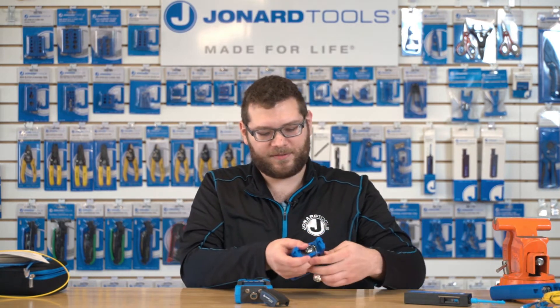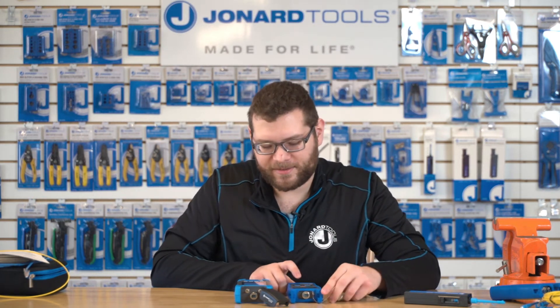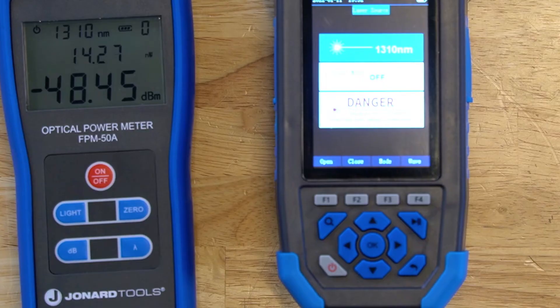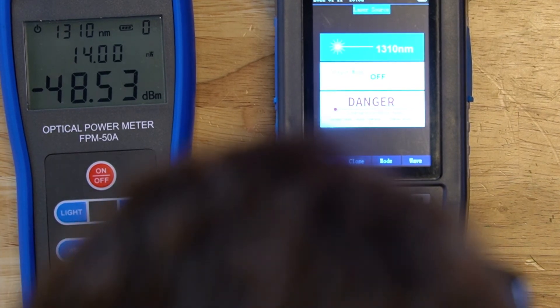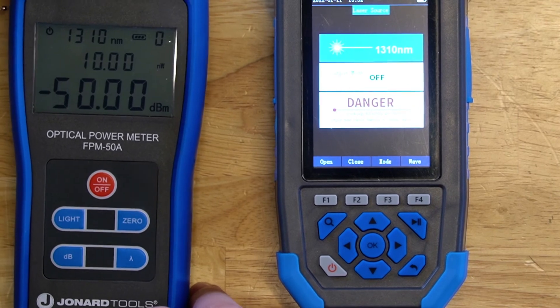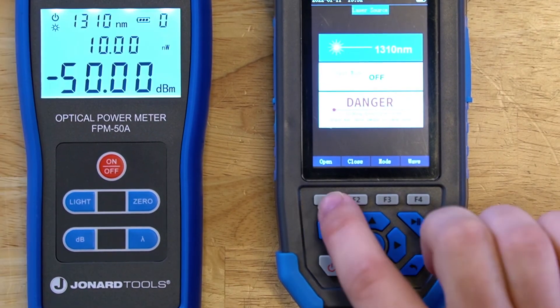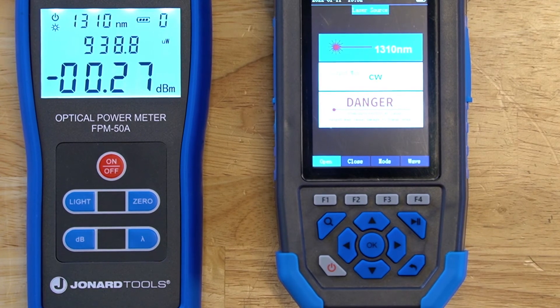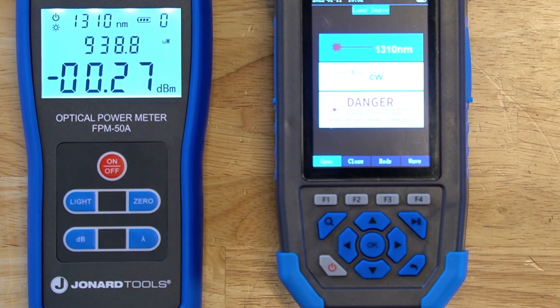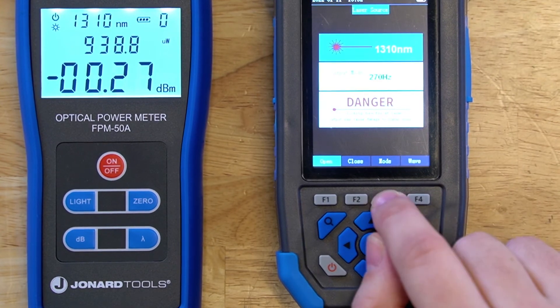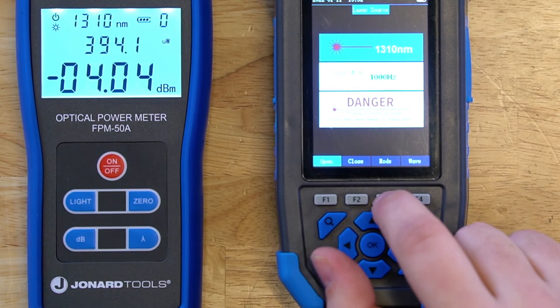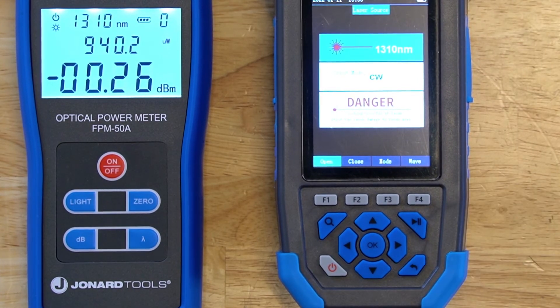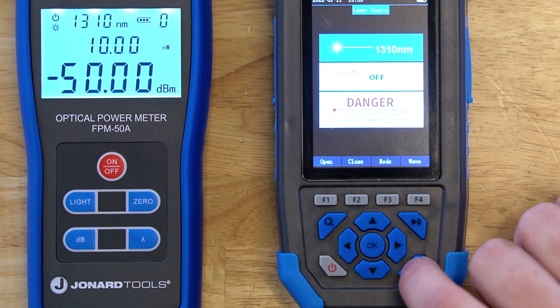The next module is the laser source module, which is the same as our FLS-50, providing a light source for single mode fibers. Connect one end of the fiber optic cable into the OTDR port and the other into the power meter port. Press F1 to turn on the laser and it will provide the light source for the power meter. You can also change the wave to 1550 nanometers and change the mode from a steady laser to 270, 330 Hz, 1000 Hz, or 2 kHz. When done, close the laser and press back.